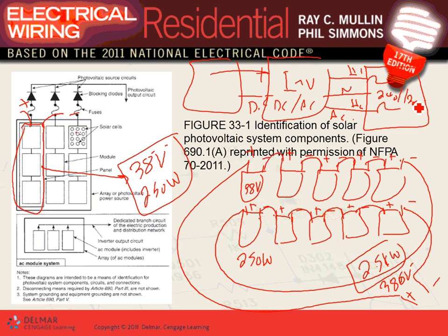They call it a string. Can you see these ends here? I have 10 of them in one string. You know what they do? They bring another string right here, and they tie in like this. Here's another, this would be 2.5 kW. Imagine another set of another 10 with two wires, and at the end, here's the first string, the second string, positive to positive, negative to negative. You have another string.